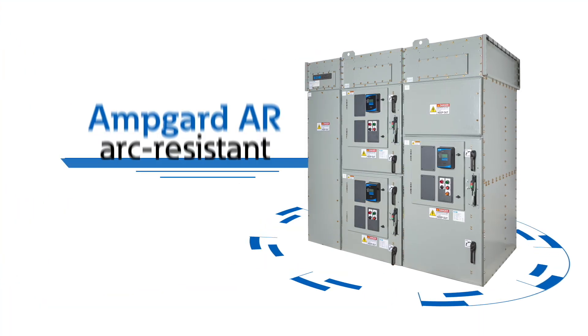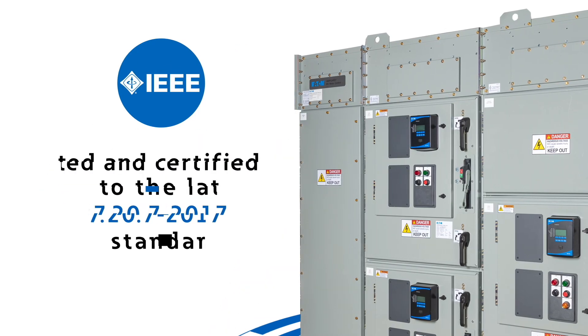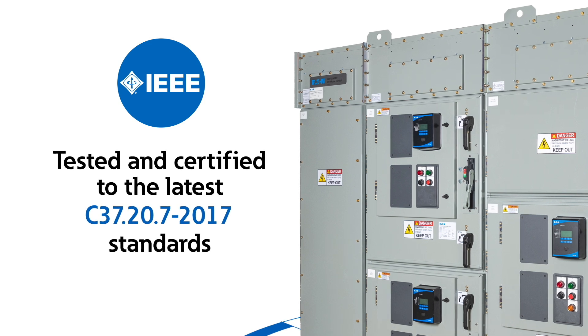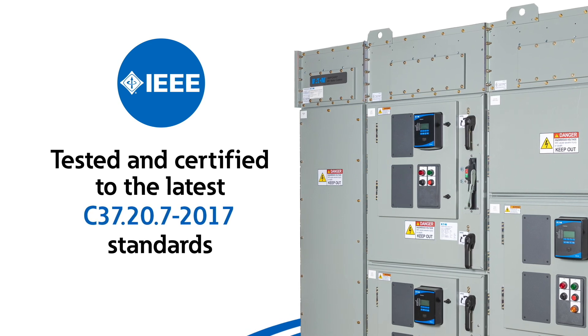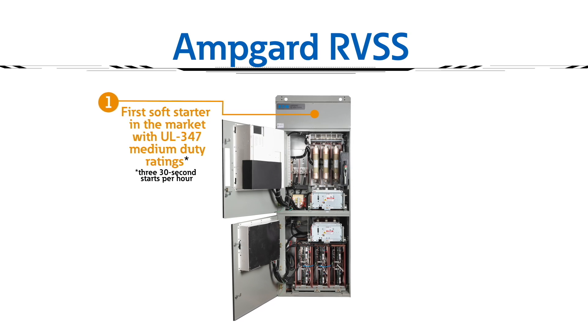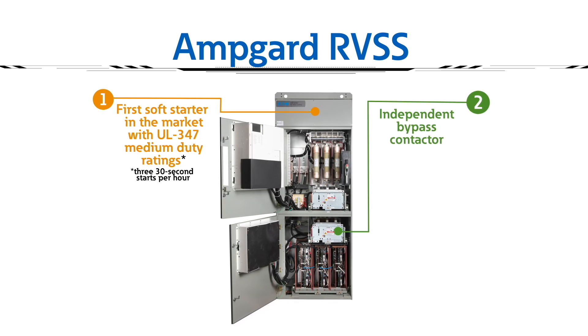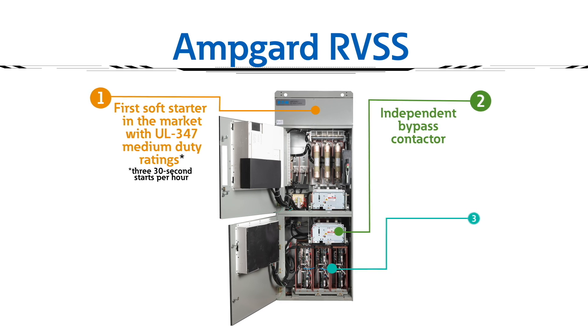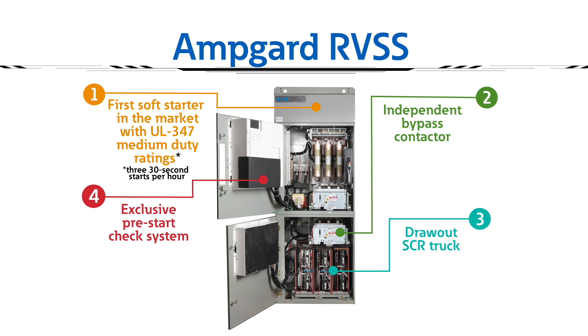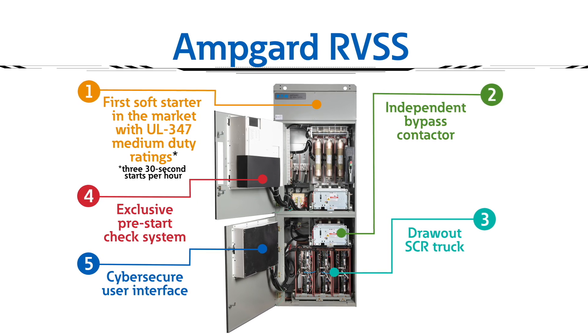Eaton's SL contactors feature industry-leading contactor interruption ratings. Latest solutions include our Ampgard AR arc-resistant enclosure, tested and certified to the latest IEEE C37.20.7 2017 standards, and our Ampgard RVSS — the first soft starter in the market with UL347 medium duty ratings — featuring an independent bypass contactor and draw-out SCR truck for ease of maintenance, along with an exclusive pre-start check system and cyber-secure user interface.